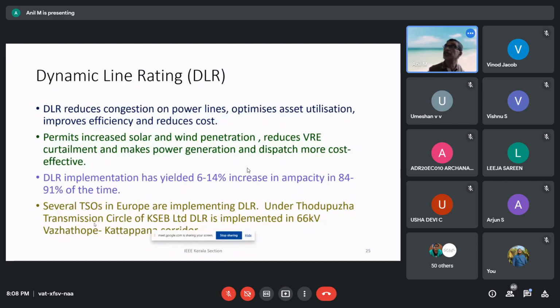Then the last solution that we are going to discuss is dynamic line rating. Dynamic line rating reduces congestion on power lines, optimizes asset utilization, improves efficiency, and reduces cost. DLR permits increased solar and wind penetration, reduces VRE curtailment, and makes power generation and dispatch more cost effective. DLR implementation has yielded a 6 to 14% increase in ampacity in 84 to 91% of the times. Several transmission system operators in Europe are implementing DLR. In KSEB Limited, under Thodupuzha Transmission Circle of KSEB, we have DLR implemented in the 66 kV Vazhathope Kattappana corridor.